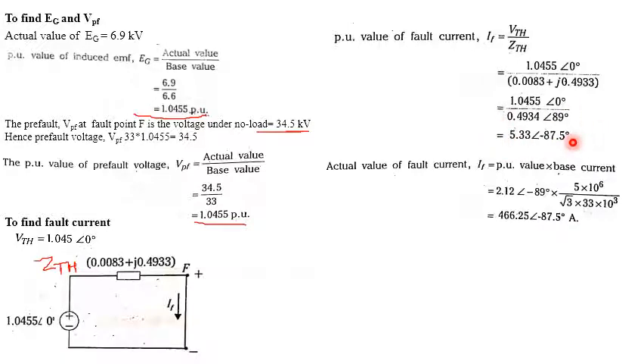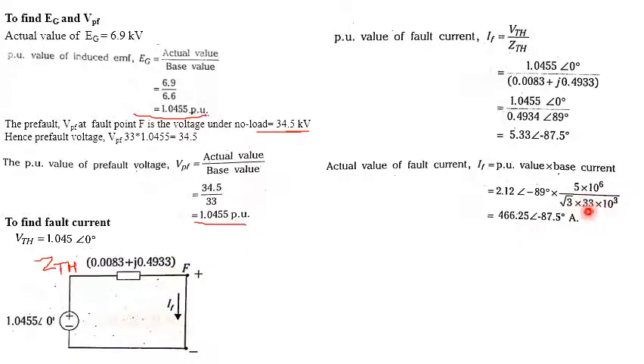To find the actual fault current, we calculate the base current at the fault location on the feeder. Base current = MVA_base / (√3 × kV_base) = 5 / (√3 × 33) = 87.48 A. Multiplying the per-unit fault current by the base current gives the actual fault current as 466.25∠−87.5° amperes. Be very careful to only calculate what is specifically asked in the examination.